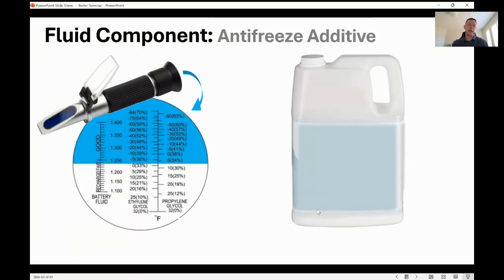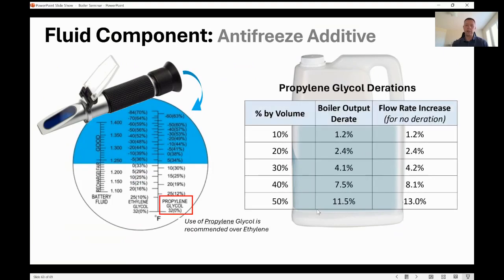Now, if you're using glycol or antifreeze, always remember that it does affect flow rates and deration. Basically, the more you put in, the more you're going to end up derating your boiler. A 50% glycol solution will derate your boiler by about 11.5%. If you're not comfortable with that deration, you can increase your flow rate to overcome it. You'd have to increase your flow rate by about 13% just to overcome that potential deration that could occur from it.